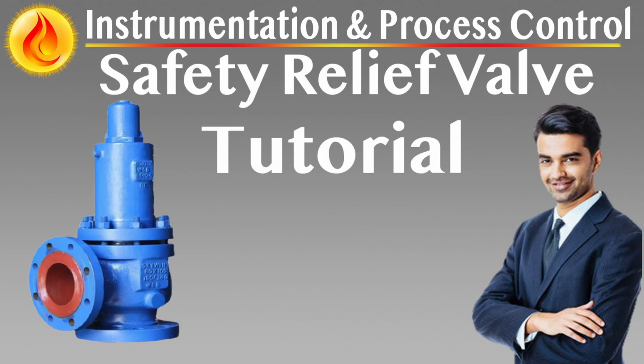Application scenarios. Air-assisted relief valves are preferred when operating pressure is close to the set pressure with only 5% margin. High process reliability is needed without sacrificing safety. Sealing performance must be enhanced without resorting to soft seats. The relief valve must open sharply at precise set pressure to minimize risk to equipment.